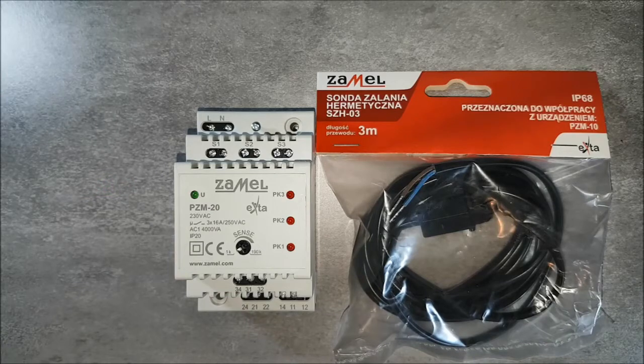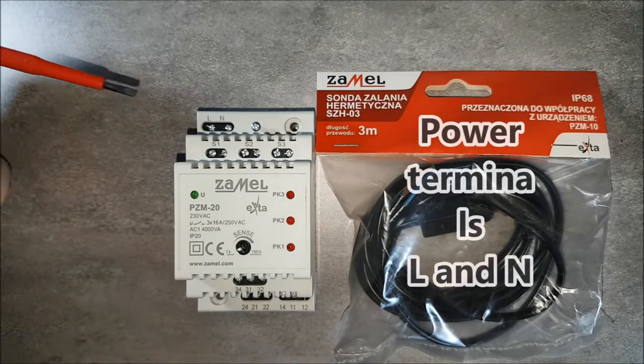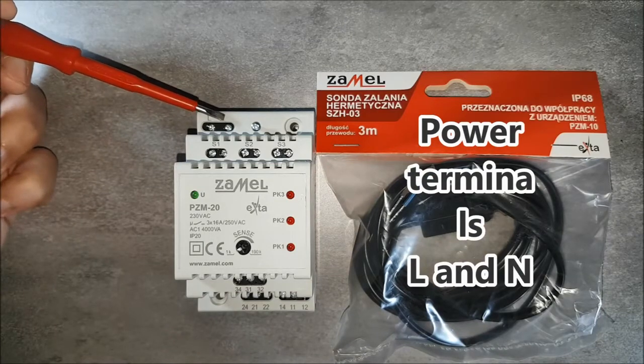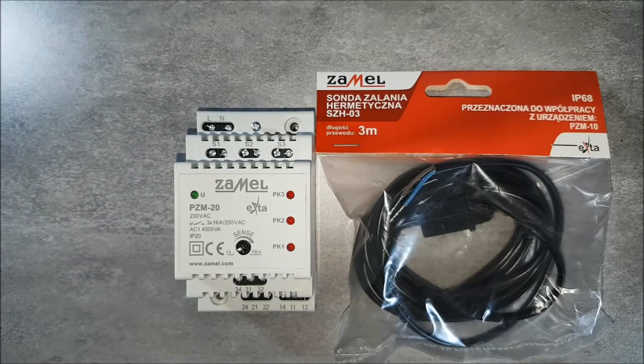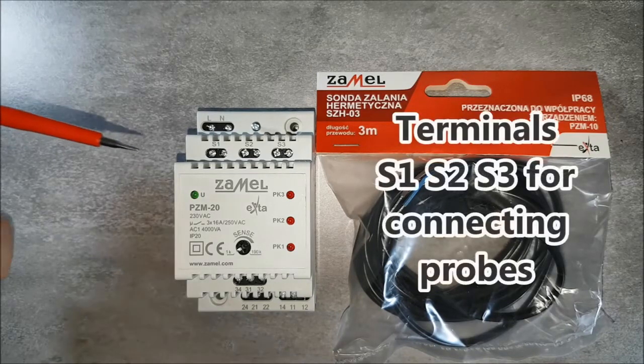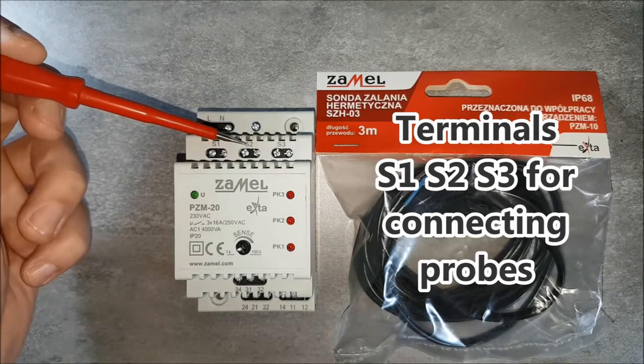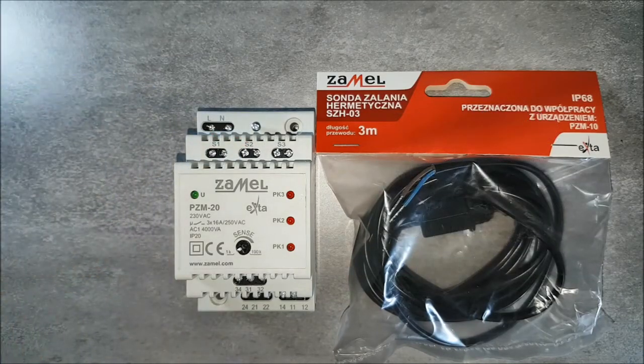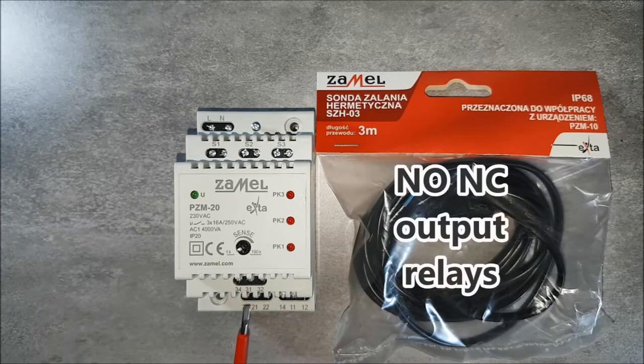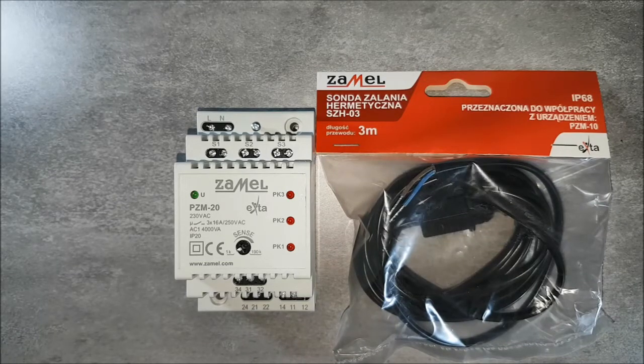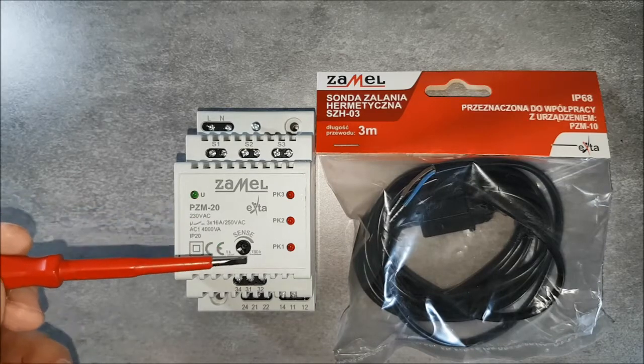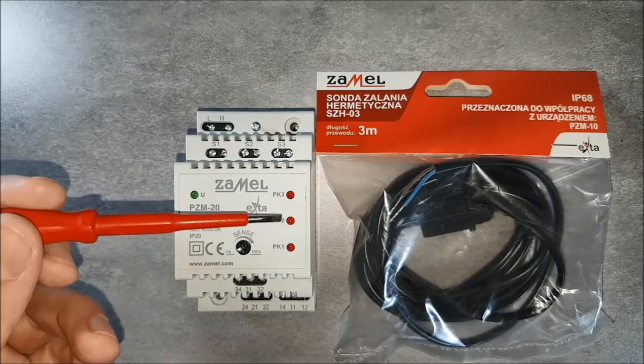The PZM-20 relay is for installation in switchgears on the TH35 rail. It is a 3-module housing. Power terminals L and N are to connect the 230 volts AC power supply. Terminals S1, S2 and S3 are to connect 3 monitoring probes. The 3 NO and NC output relays work independently of each other. The status of the output is given by red LEDs.